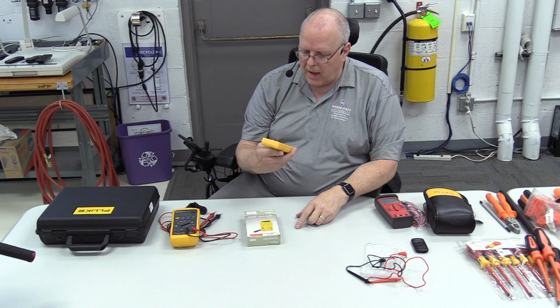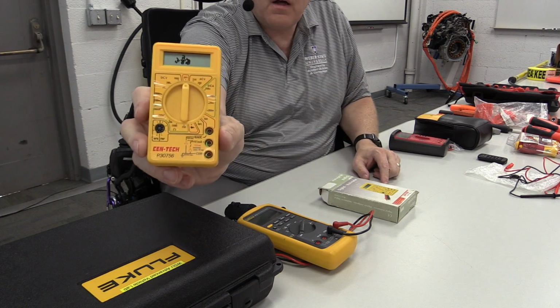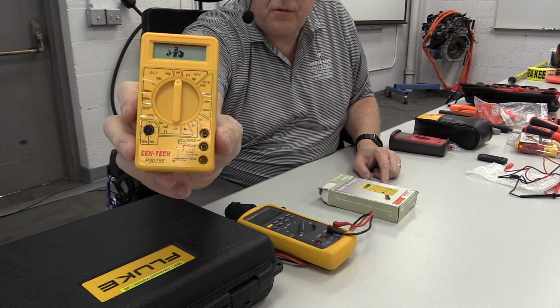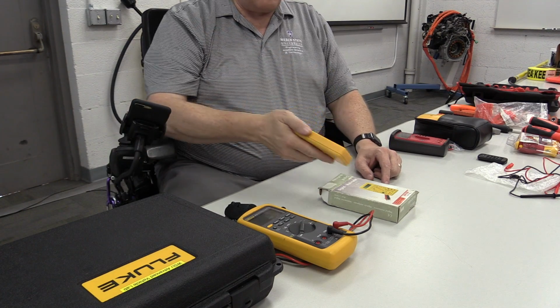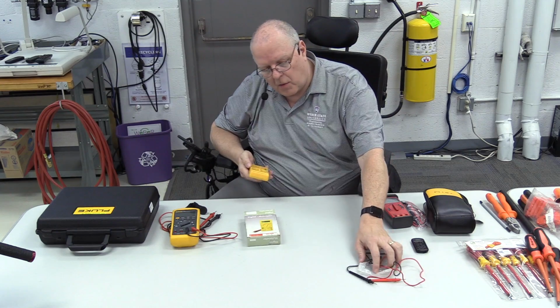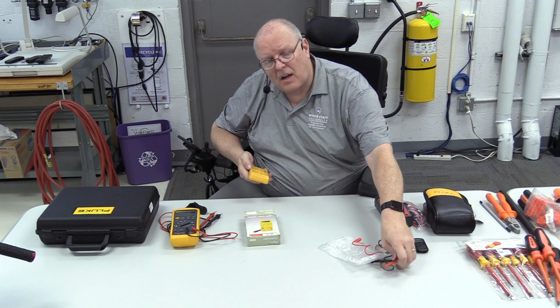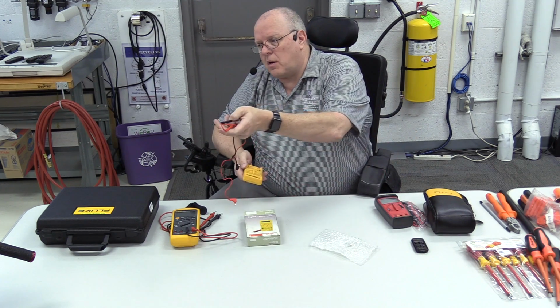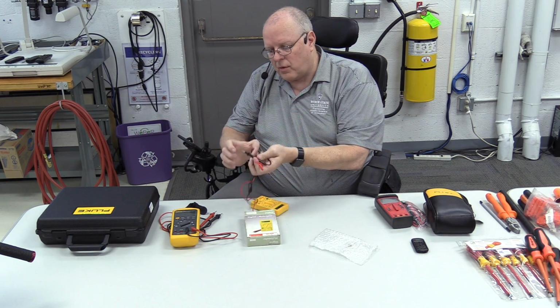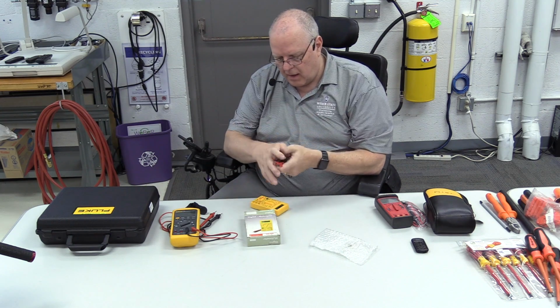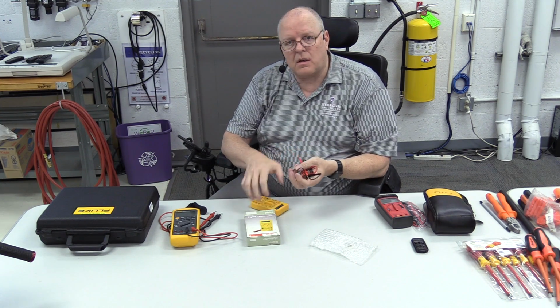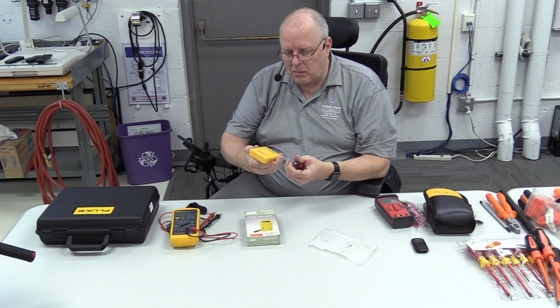It has no category ratings at all on the meter itself. The owner's manual or the instructions that come with it say nothing about category ratings. The meter leads themselves say 1000 volts, but there's no category there, and I wouldn't trust it at all to be safe to use on high voltage.